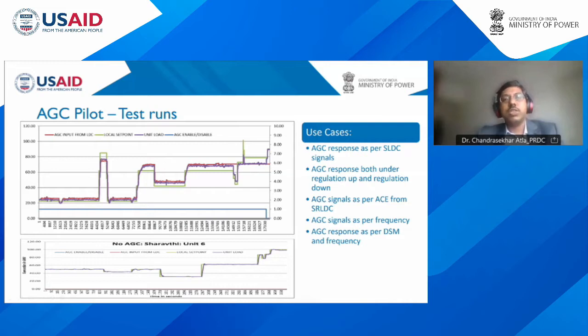We have made many checks because we have to make sure that generators operating under AGC do not get any other implications. We have made one check at SLDC so that it won't cross the ramp rates of the generators. Also at the plant side, we have made a couple of checks, so that at any point of time the AGC signal will not go beyond the maximum or below the technical minimum. Similarly, at a given time, the AGC response can be set by the operator to 5% or 10% max. So if the unit is generating at 80 megawatt, you can ask for the AGC response.